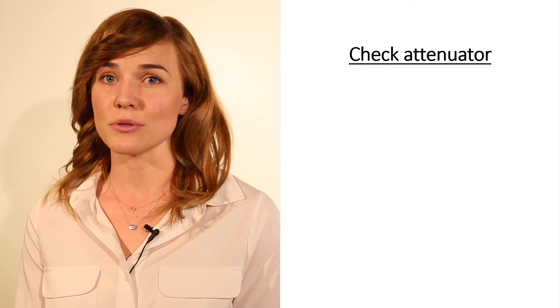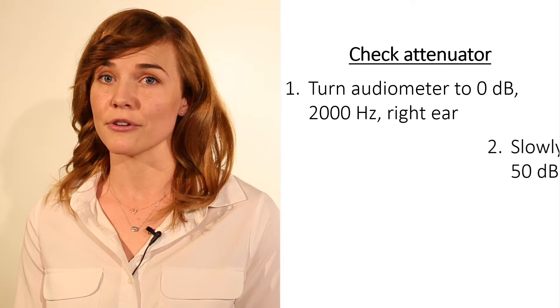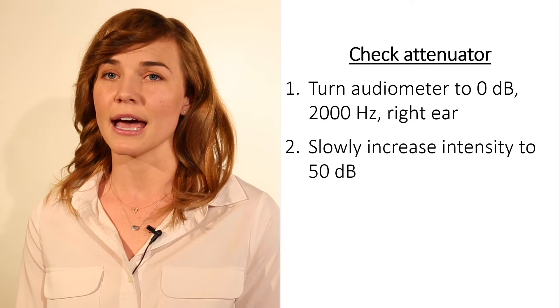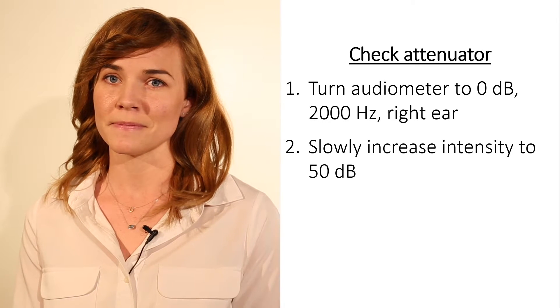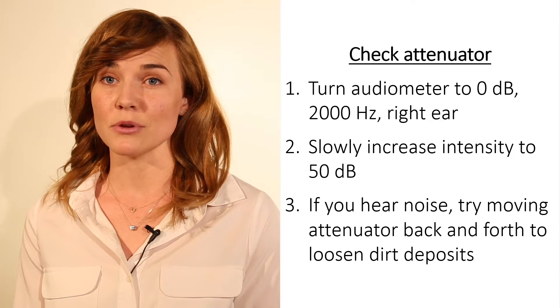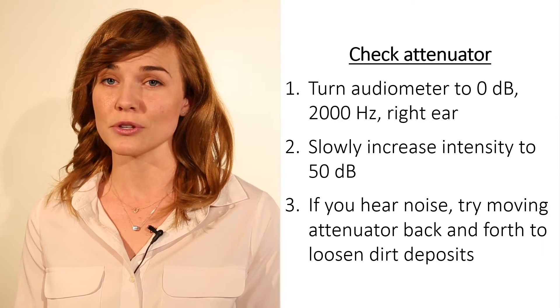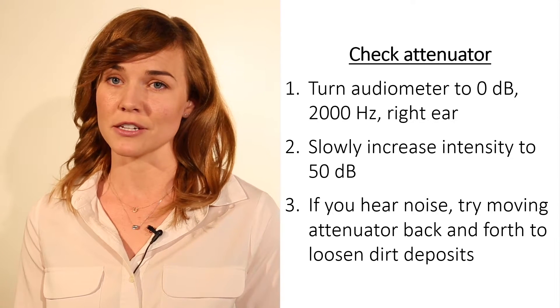Finally, check for noise from the attenuator. At 2000 Hz, slowly increase the attenuator from 0 to 50 dB and listen for a scratchy noise. If necessary, rapidly move the attenuator back and forth to loosen any dirt deposits. This should resolve the issue.